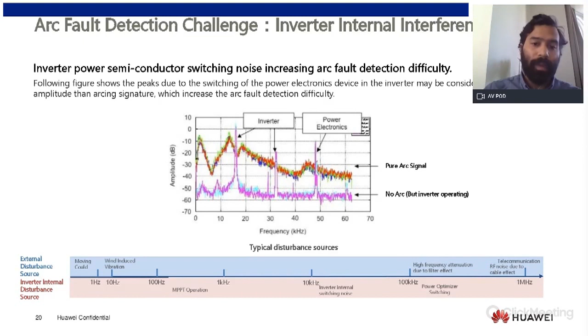So in practice, the problems this will cause are, for the installer, for example, a lot of complaints because the system is falsely tripping, or is actually not detecting the arc fault and is creating some hazard for the building. And when there is false tripping, you will need to go continuously to site to do some troubleshooting and maintenance. And of course, as we know, this comes with a related cost. This is for the installer.